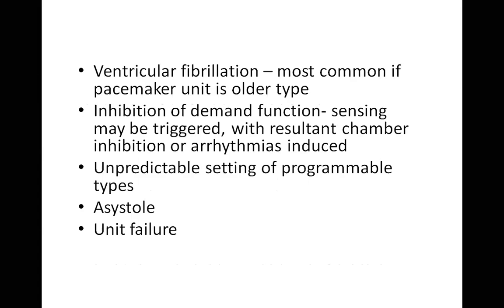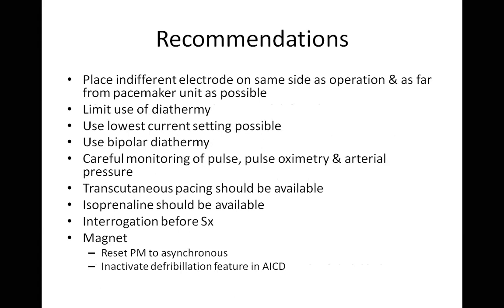The patient can go into asystole. So it's recommended that if you're going to use diathermy, use the bipolar diathermy. Don't use monopolar. It has less electrical activity generated when you use bipolar. The number 2 thing you can do is to put the patient on VOO, which we have previously explained. Another thing you can do would be to put a magnet. So that's the importance of the magnet. You can put a magnet on the pacemaker battery or an ICD, and it will go into VOO mode immediately.